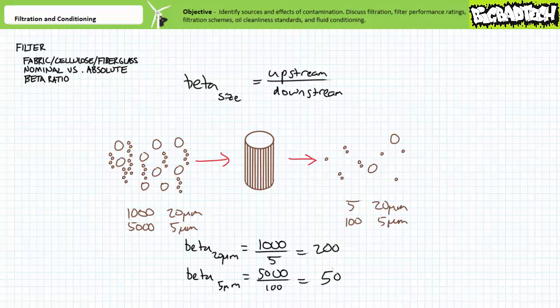If this same test was performed for particles larger than only 5 microns, the filter might have a different beta ratio. Consider a filter with 5000 particles larger than 5 microns in size upstream and only 100 particles greater than 5 microns in size downstream. This filter therefore has a beta ratio of 5000 over 100 or 50 for particles 5 microns and above. Again, note I specified a beta ratio and a size of interest. Note more particles were filtered out simply because smaller particles were more numerous. However, the lower beta ratio expresses a smaller proportion of the available smaller particles were filtered out.